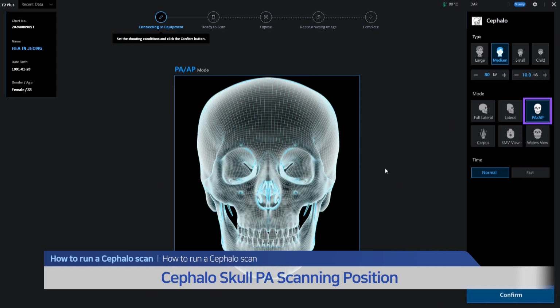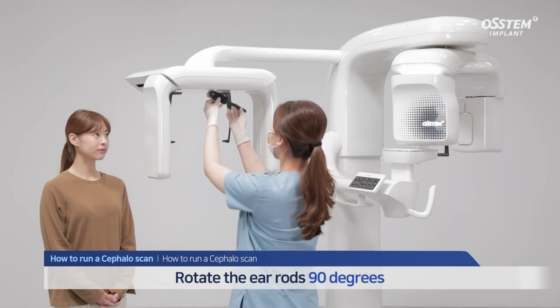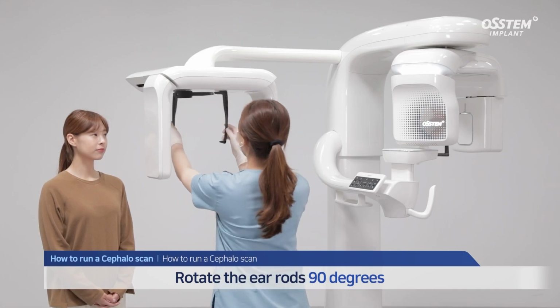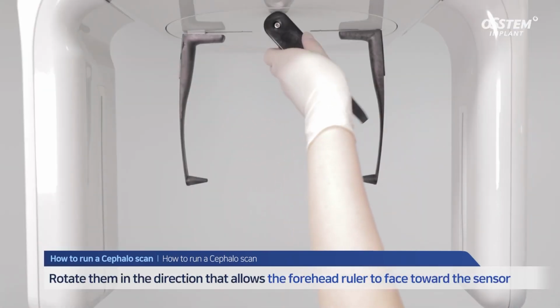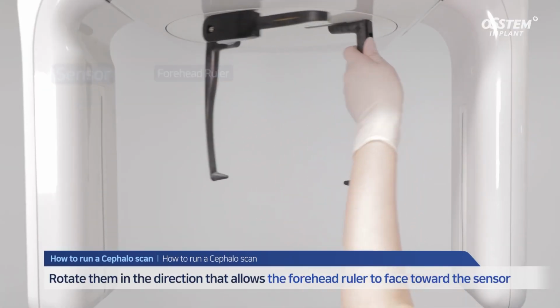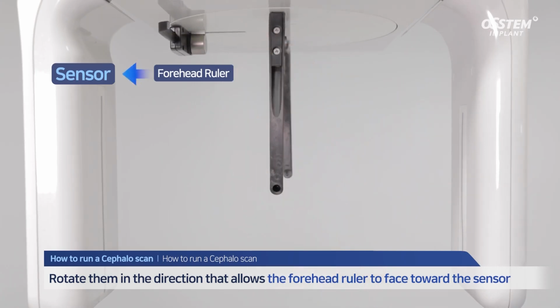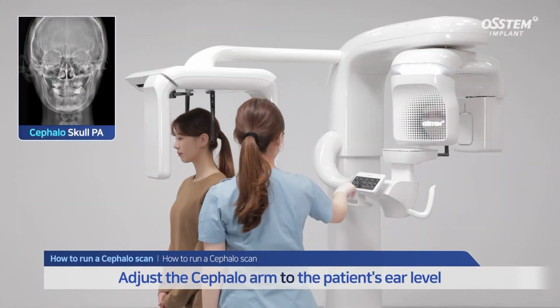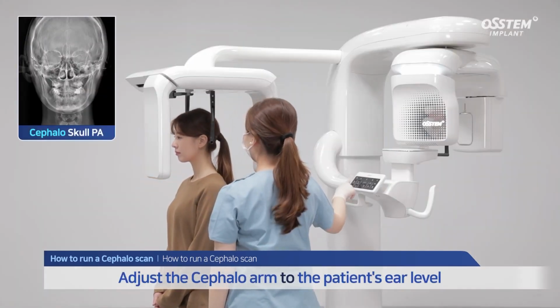Now, let's take a look at the cephalo PA scanning position. Hold the ear rods and rotate them 90 degrees. Rotate them in the direction that allows the forehead ruler to face toward the sensor. Raise the forehead ruler upwards. Adjust the cephalo arm to the patient's ear level.